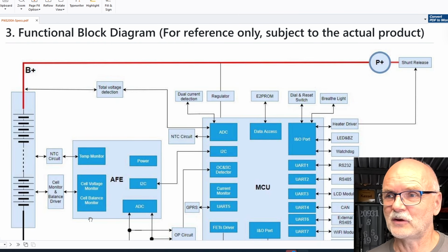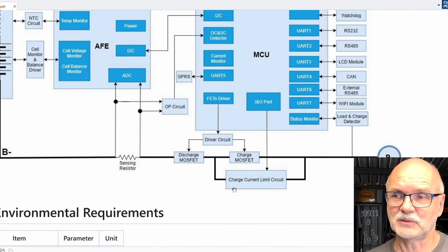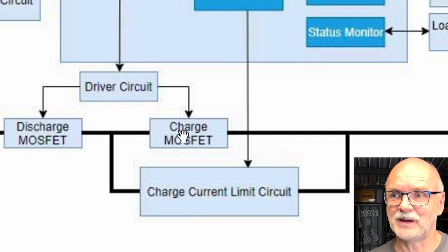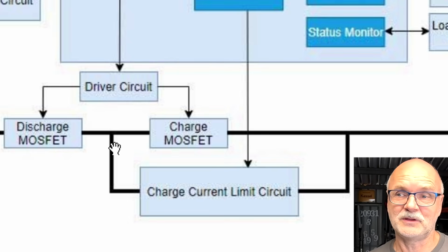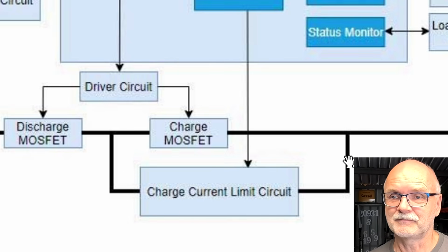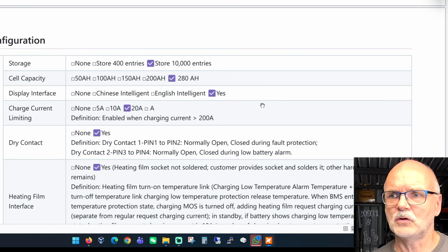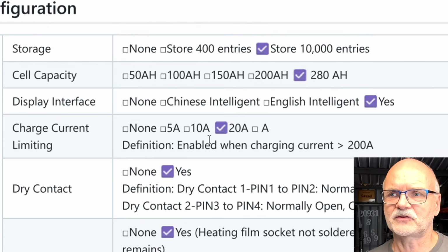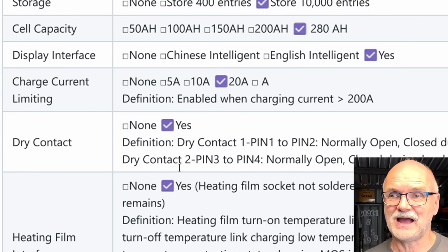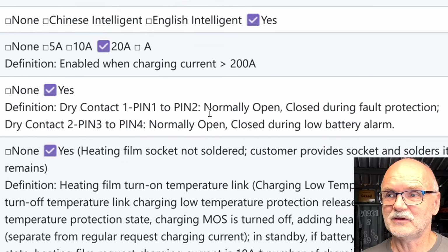So here's a block diagram so you can roughly see how it works. Here we can see the charge current limiter here is bypassing the charge MOSFETs. So even if they turn off, we can still get some power into the battery through this charge current limiter. Okay, basic configuration. So let's have a look. Charge current limiter 20 amps, dry contacts, so they are hard coded. So we cannot specify when these 2 relays are coming on. Dry contact 1 normally open, closed during fault detection, and the second relay normally open, closed during low battery alarm. I think this was the same functionality with the other BMSs as well.